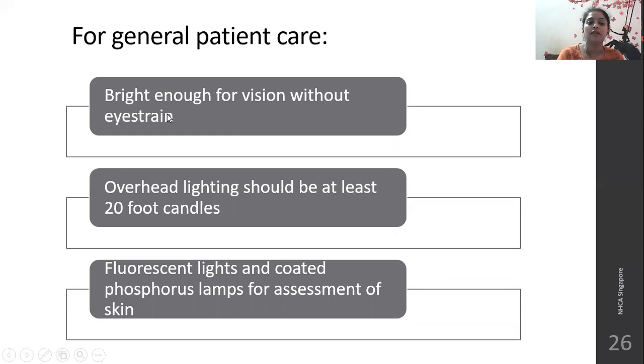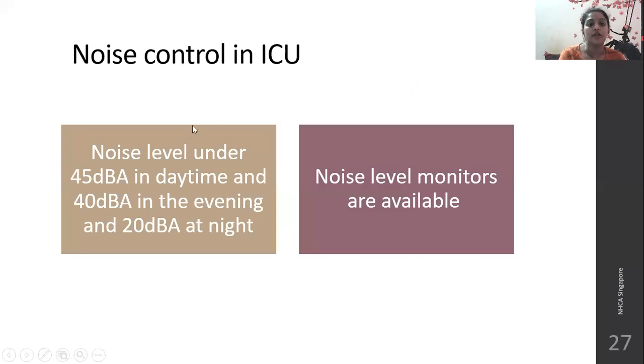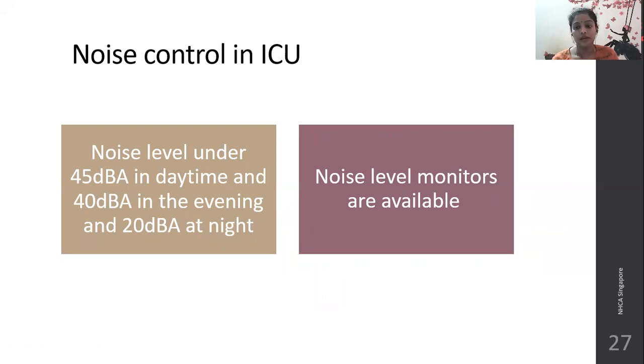For lighting, natural light is preferred. Artificial daylight can be installed for night workers so that circadian rhythm is not affected. For procedures, high illumination with shadow-free spot lighting should extend from the ceiling or walls, with at least 150 foot-candles of illumination. For general patient care, overhead lighting should be at least 20 foot-candles. Fluorescent lights coated with phosphorous lamps can be used for assessment of the skin. The noise level should be under 45 A-weighted decibels during the day, 40 in the evening, and 20 at night.